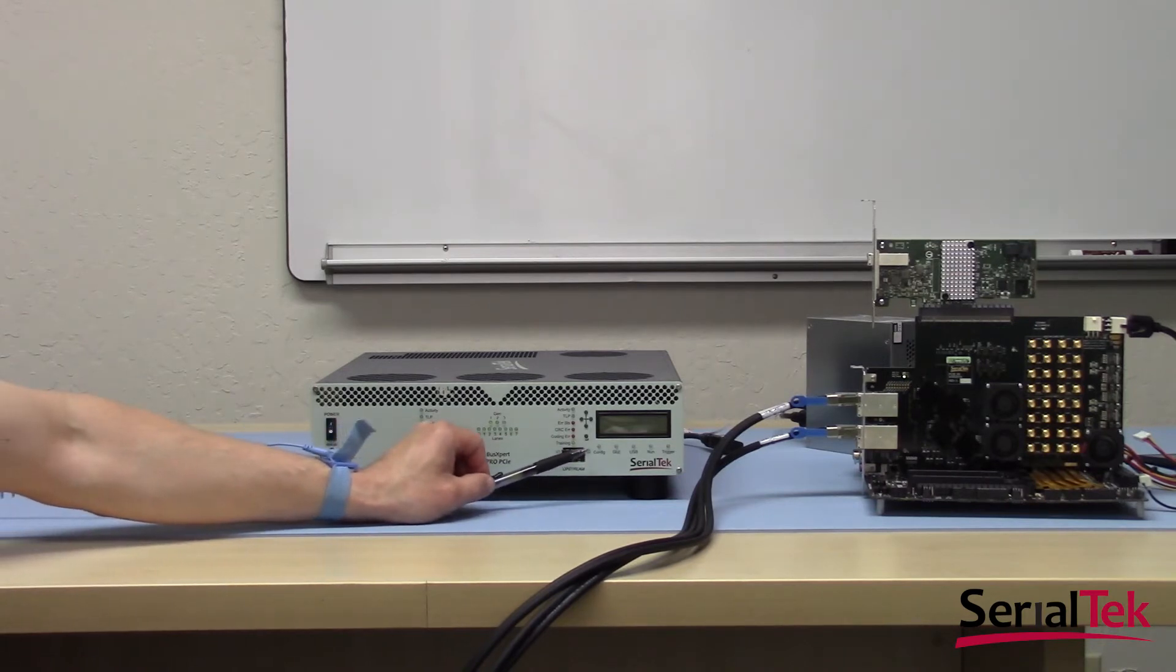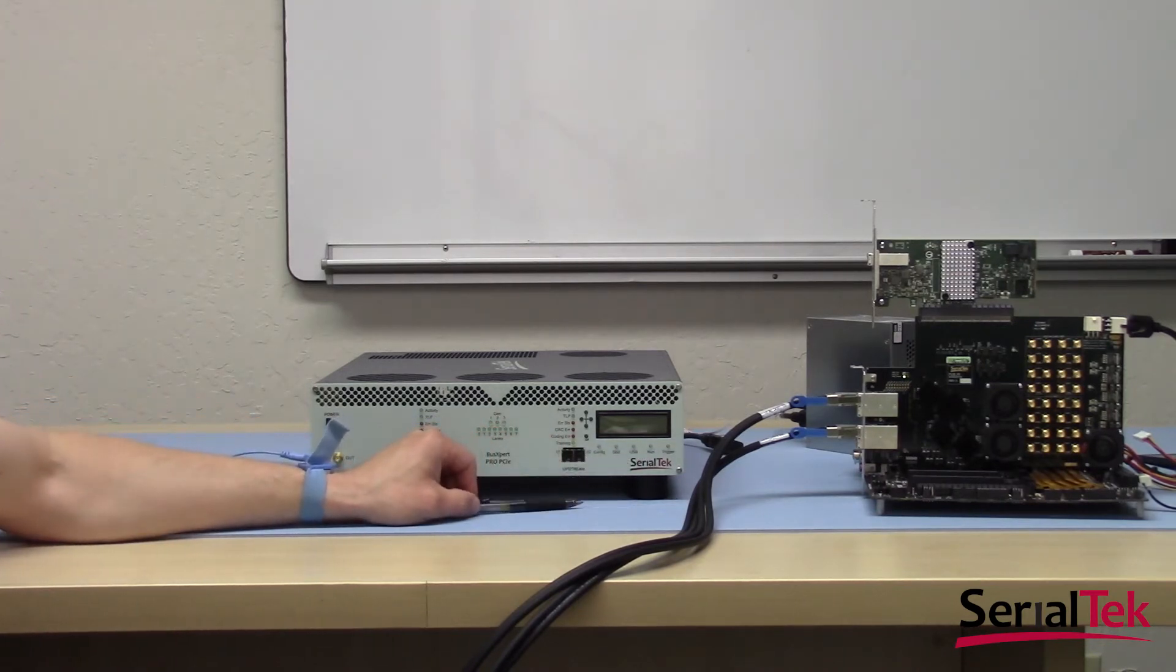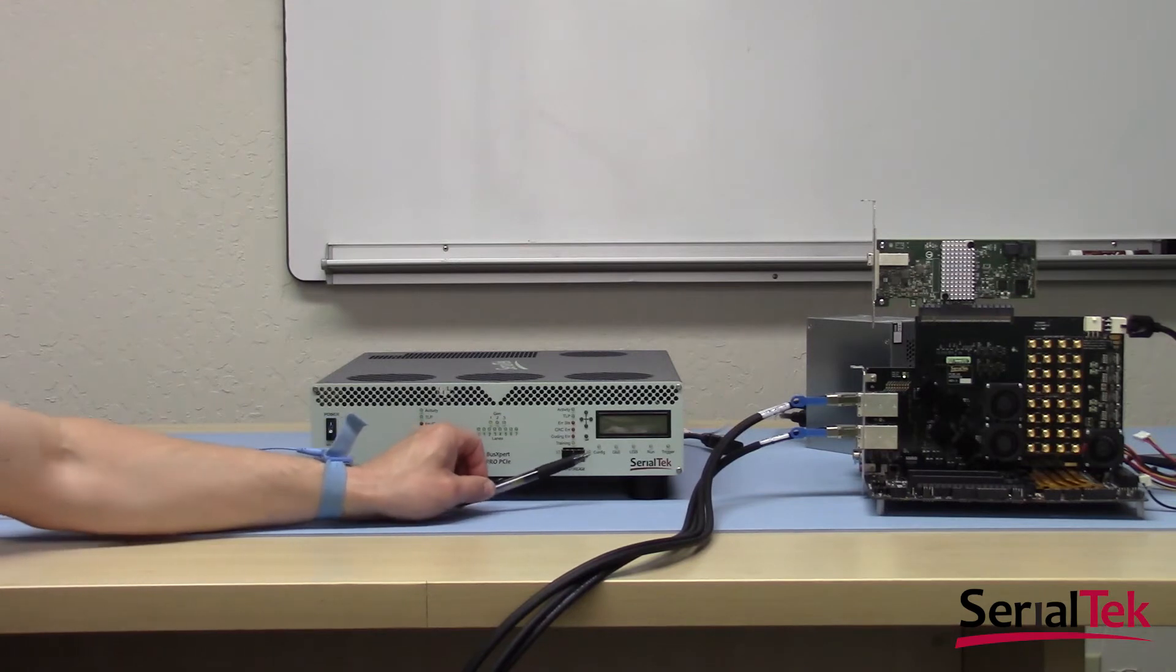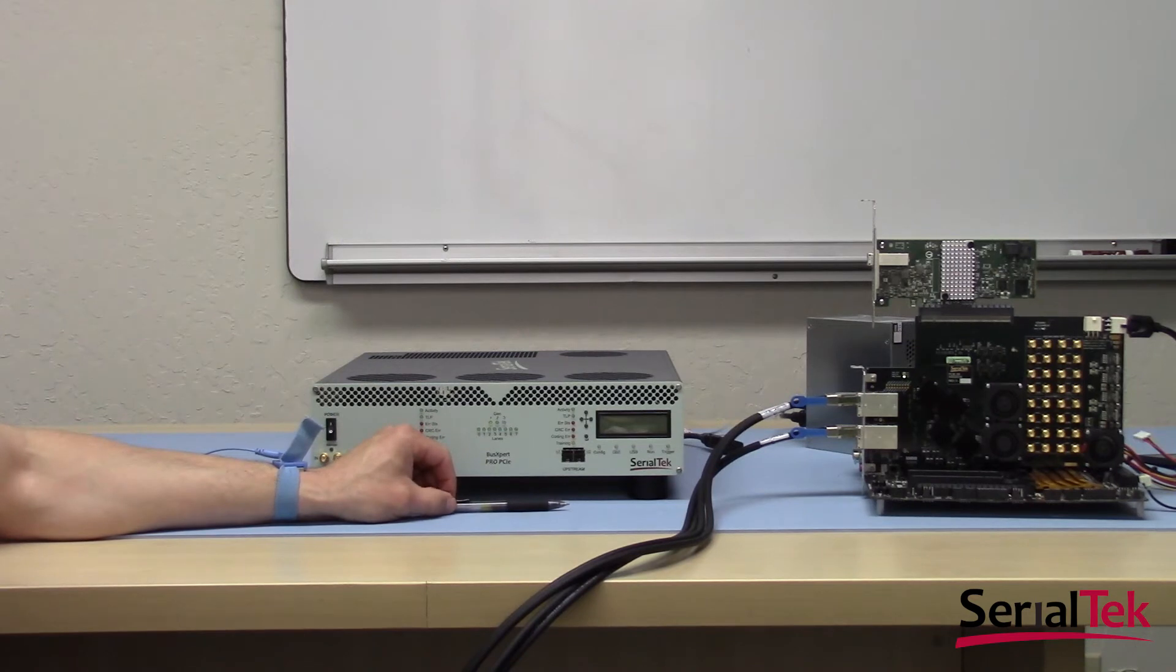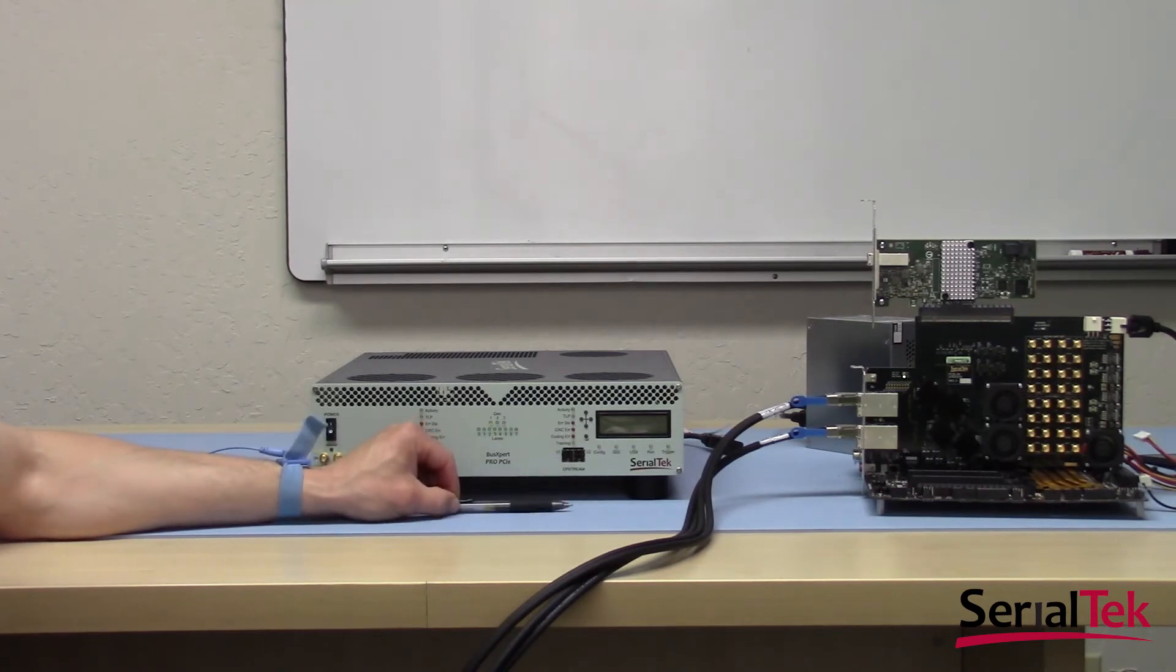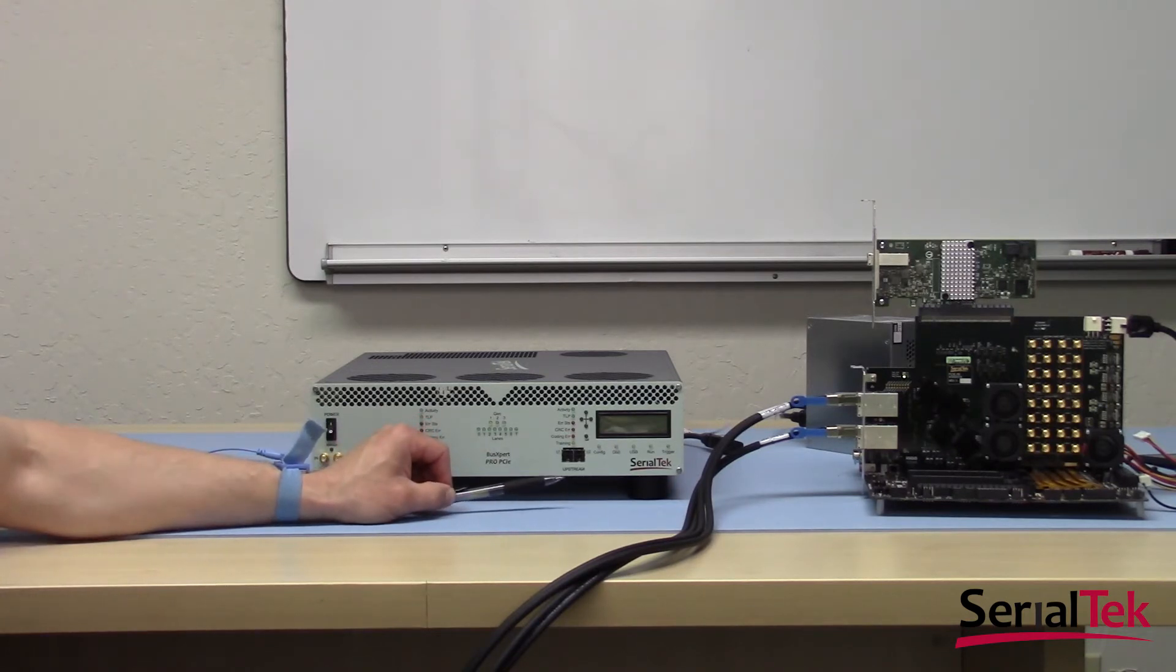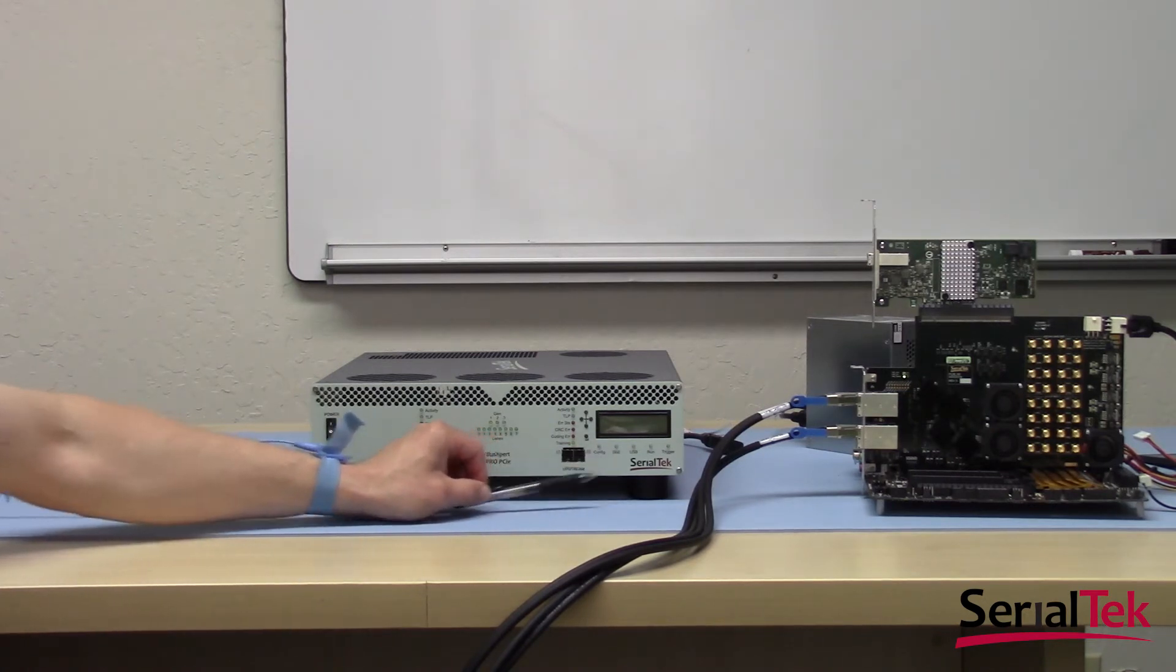And lastly, directly below the LCD display, there are a set of LEDs that show the current status of the analyzer in real time. So these system status LEDs, the first is config. This will light green when the analyzer is successfully turned on and the FPGAs inside are initialized and ready to go. If that light is red, then we'll need to contact support or perhaps consider the factory reset option via the rear panel that we described in the segment on the rear panel.